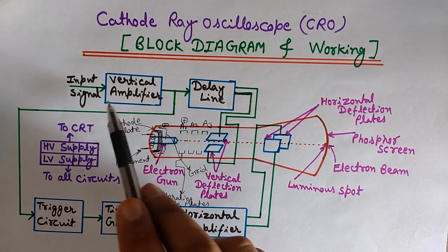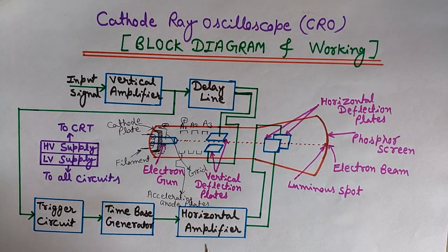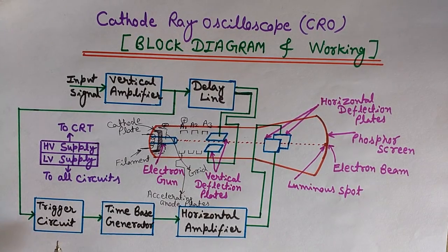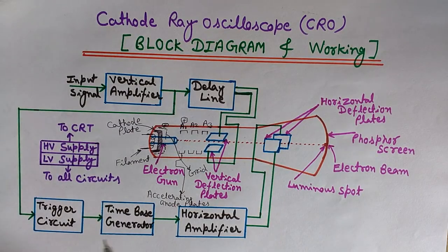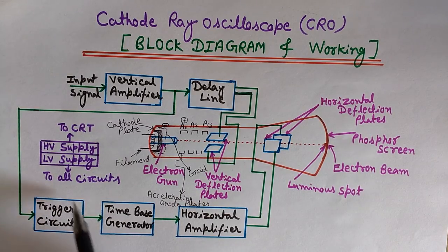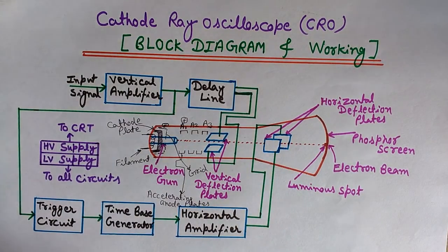After the delay line, the input signal is applied to the vertical deflection plates. The trigger circuit is provided for synchronizing the two types of deflections — vertical deflection and horizontal deflection — so that the horizontal deflection starts at the same point of the input vertical signal each time it sweeps. Synchronization is the purpose of the trigger circuit.